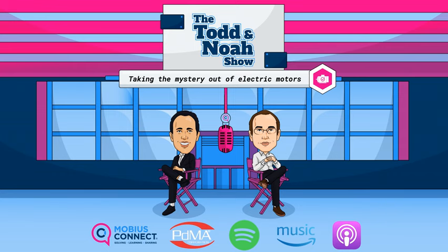Well, our favorite standard of reference is the IEEE 519. IEEE being the Institute of Electrical and Electronic Engineers. Okay. They're well known and respected around the world, really. Them and IEC and a variety of others. But IEEE is a good reference. 519 does a great job in terms of breakdown of harmonic limitations. And so, as many vendors would do, they look at some of the bodies of knowledge and the standards to build in their alarm set points, and we're no different. So a lot of our initial, out of the chute alarms that are established come from that 519.